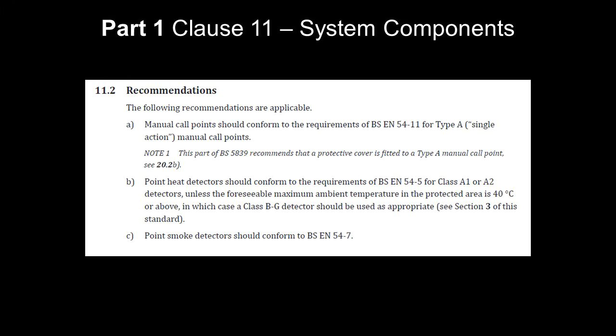And what we'll go through on part 1 clause 11, system components, this clause basically lays out the product standard for what detectors can be installed and how they're manufactured. So each detector has to be installed to a standard, okay? And this clause outlines what detectors can be used within part 1. So commercial premises fall under part 1, not part 6. And in a nutshell, domestic smoke detectors are not approved for part 1 systems in part 1 premises. And if we go to part 6 here, we can see that there are some, you're allowed commercial detectors and alarms to be used in part 6, but generally not the way around.